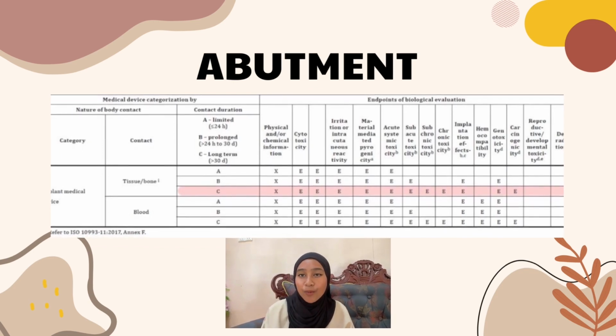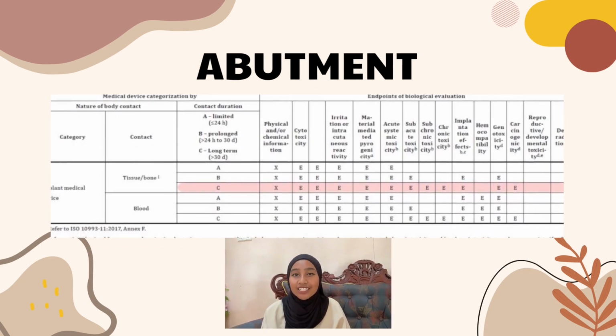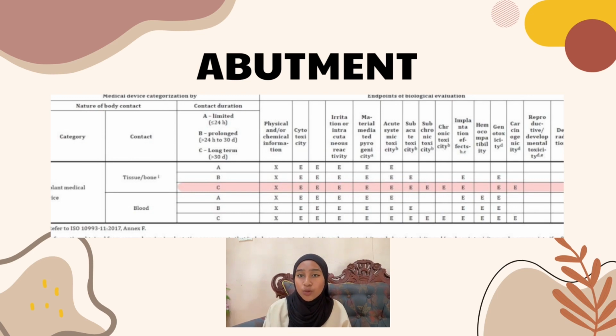Today I'm going to talk about biomaterial approaches in dental implant abutment. When referred to ISO 10993, categorizing medical devices according to the nature of body contact, contact duration and endpoint of biological evaluation, the abutment is in the category of implant medical device for contact in tissue bone, with contact duration that is long term. Endpoints of biological evaluation in this category include physical and chemical information, cytotoxicity, and others.